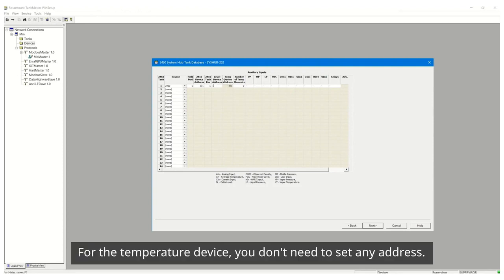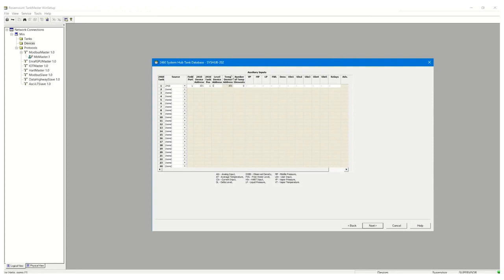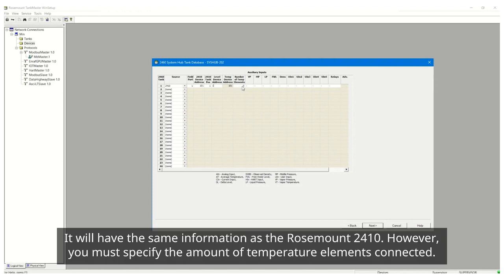For the temperature device you don't need to set any address. It will have the same information as the Rosemount 2410. However, you must specify the amount of temperature elements connected.